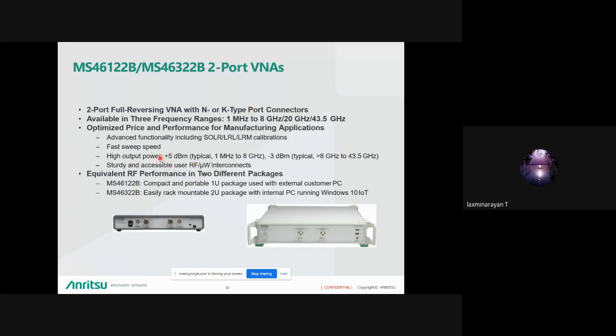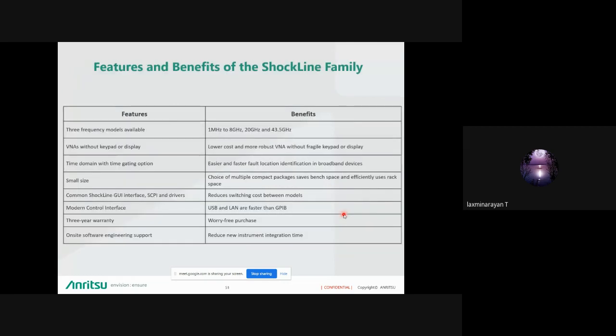As I told, it can go up to high power up to plus 5 dBm and low power up to minus 3 dBm. It will cover all the OSLR, SOLR, LRL, LRM calibration, and it is fast. It is a 1U package which will be used for most of the education customers, and they are using it for a field application where you can carry it in a bag and just connect to your laptop and use it. And this is used for a manufacturing production area where it will be rack mounted, 1U size, 2U size, and it will be connected to an ATE setup, and they will control through their PC and they will run it in the production areas.